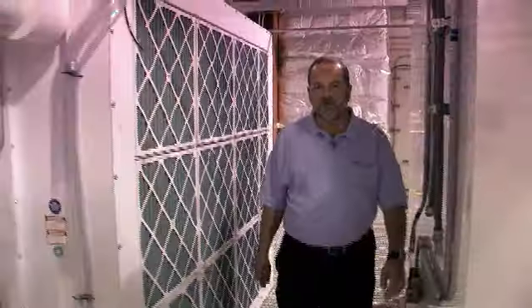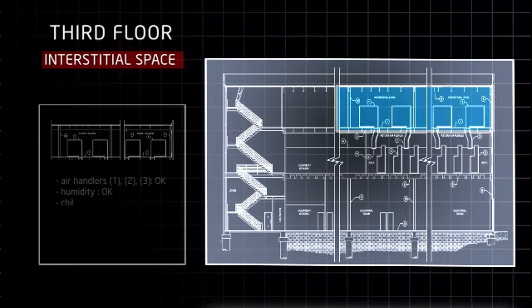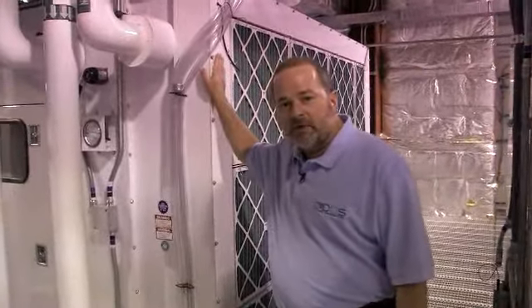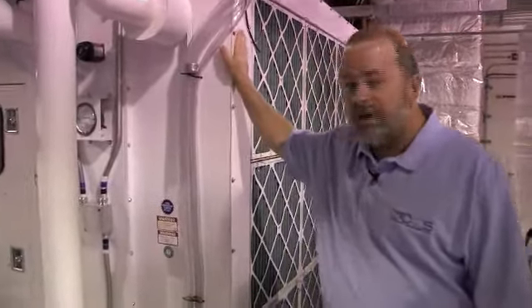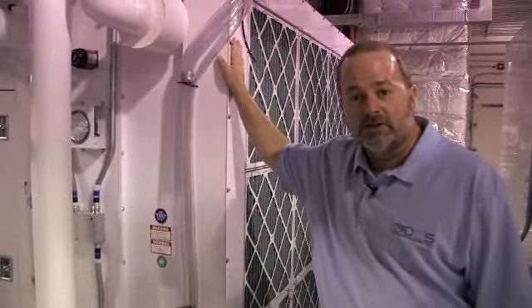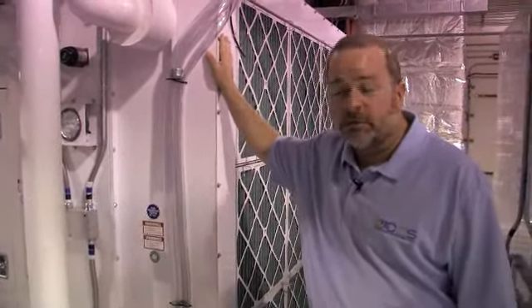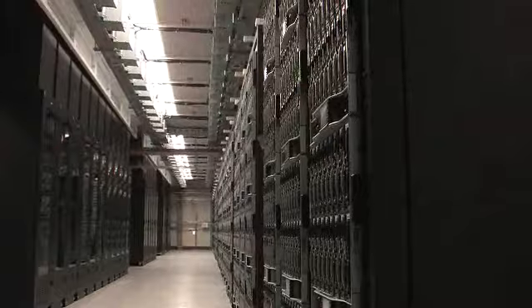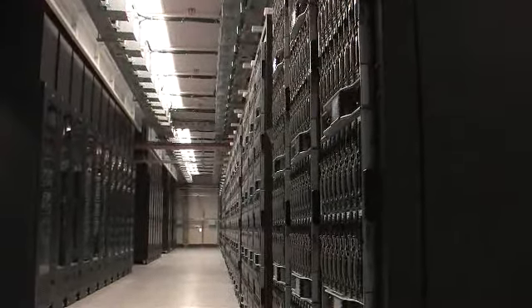We're on the 3rd floor of the factory building that we retrofitted for our computer room. This is also called the interstitial space, where we have all the air handling units. We added capacity by putting another chilled water coil on the back of these existing air handling units to meet our cooling needs. We also gained valuable floor space in the computer room by not having to put in computer room air conditioning. So we used the factory to our advantage.